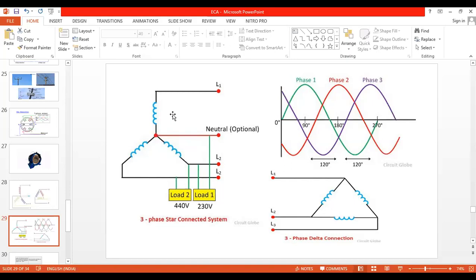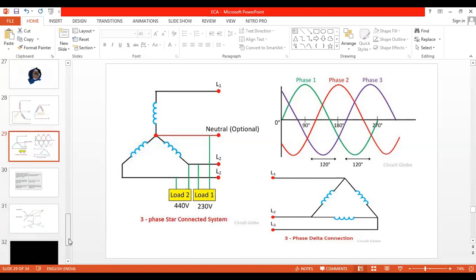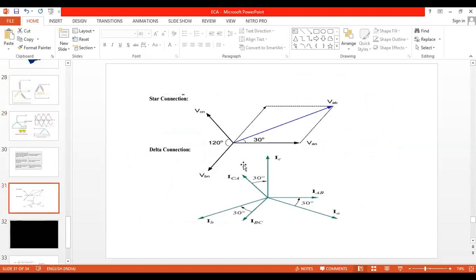Three-phase system is used to rotate machines and provides more energy than single-phase. It generates three different voltages displaced by 120 degrees. In India, the line voltage is 400 to 440 volts for three-phase, but for domestic applications combining any line and neutral gives 230 volts. We have to explain how 400V is converted to 230V using the vector diagram.